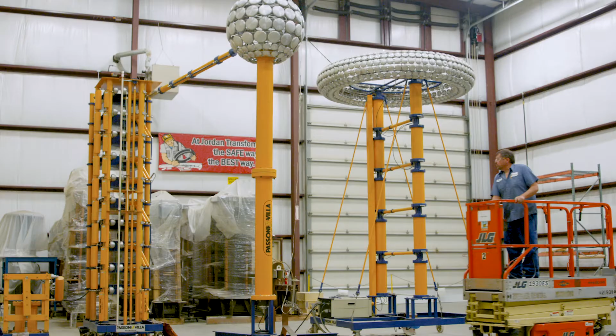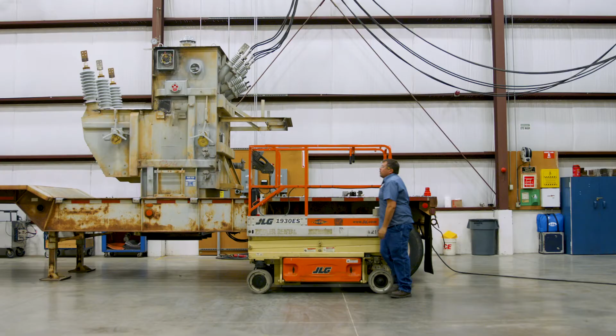We do have the ability to do all IEEE prescribed Class 2 testing, including impulse testing and partial discharge monitoring during the 1-hour induced test. So because of that, the Class 2 transformers that fail around the country end up here.